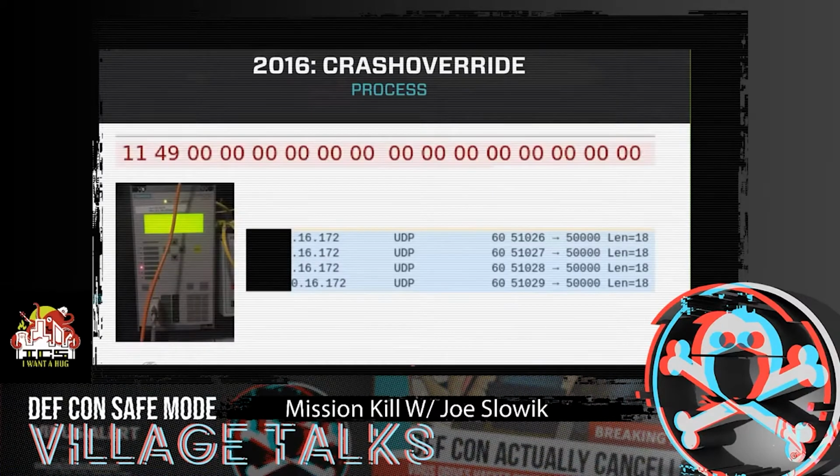So looking at the event in Ukraine, the Siemens SIPROTEC denial of service is pretty interesting in that it doesn't take the device offline, but rather the denial of service wipes all the protective logic from it. It's one of those, this is a feature as opposed to a bug, in that it's used to free up memory to allow for a firmware upgrade or a reprogramming of the device. So the device is still network accessible.